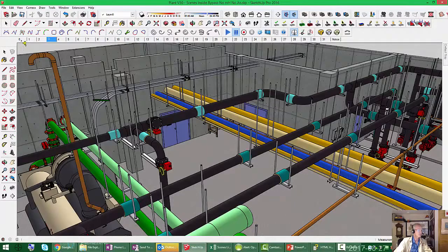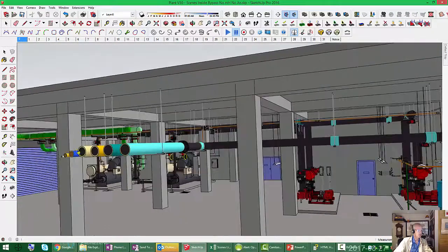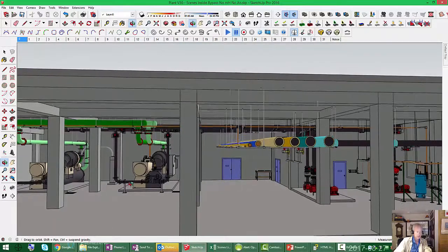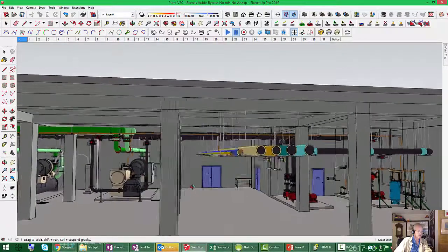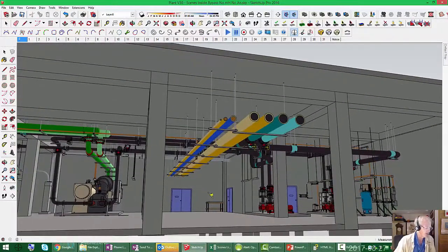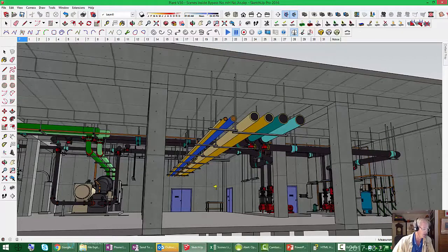And so you've walked into a mechanical room, you're at the door, and you're seeing something like this. And so what do you do? How do you get started? And the trick for me is just to find a spot you can identify and come back to that is related to the system you're trying to trace out. Put your hand on it, put your pencil down on your paper, and draw a line.